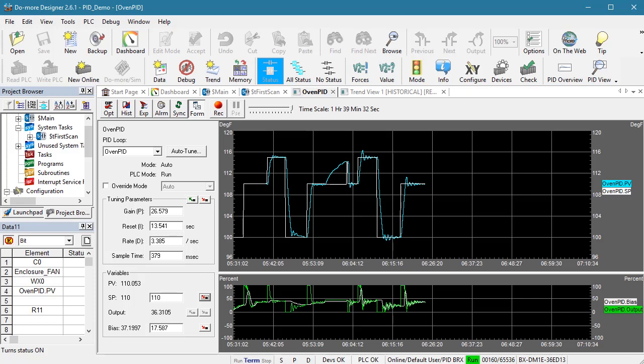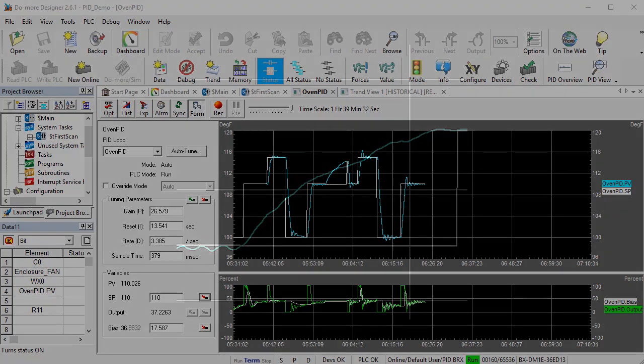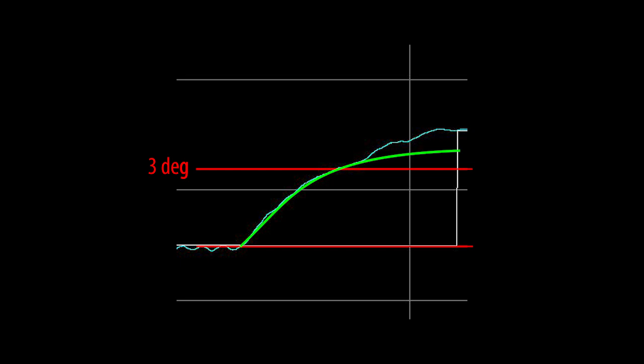Now did you see what happened here? We told Auto-Tune it could take its measurements after 3 degrees. But it went quite a bit further didn't it? Why? Well, when it hit the 3 degree mark, it started looking for the slope to flatten out. But instead, the slope actually started getting steeper, didn't it? And that's the key point of this open loop Auto-Tune – it's watching the rate at which the slope of this curve decreases. As long as it's increasing, it can't take its measurements.